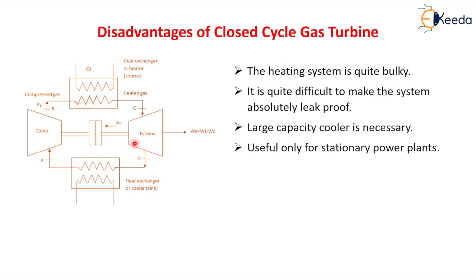Now let's see some disadvantages of closed cycle gas turbine power plant. The heating and cooling system is quite bulky. It is difficult to make the system absolutely leak proof — since the closed cycle works at high pressure, there is a chance of leakage somewhere. A large capacity cooler is necessary. The closed cycle is useful only for stationary power plants and is not useful for marine applications.